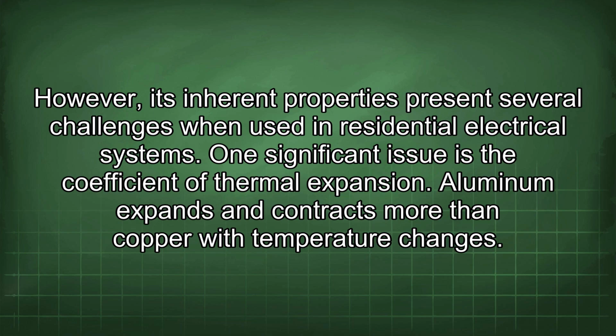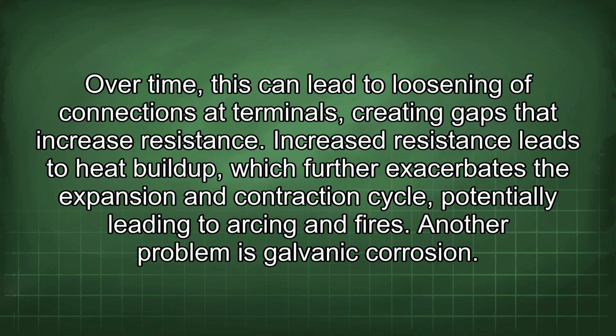One significant issue is the coefficient of thermal expansion. Aluminum expands and contracts more than copper with temperature changes. Over time, this can lead to loosening of connections at terminals, creating gaps that increase resistance. Increased resistance leads to heat buildup, which further exacerbates the expansion and contraction cycle, potentially leading to arcing and fires.